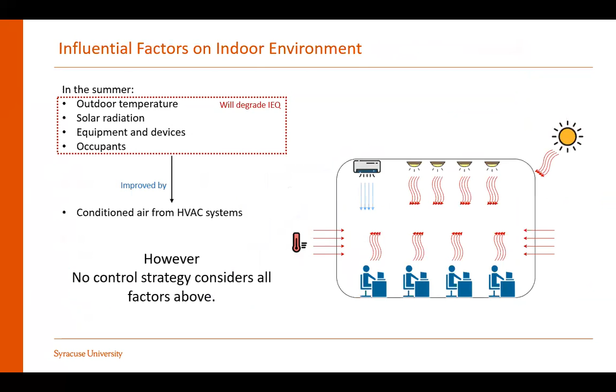For outdoor air quality, we measure those pollutants typically regulated by EPA: PM2.5, NO, NOx, ozone. Those have to be measured. Indoor, we also measure CO2, and the exchange rate is based on indoor air quality. There was a study looking at integrating ventilation and air filtration based on measurement, using this field aspect to see whether we can save energy based on outdoor weather conditions, pollution conditions, as well as indoor occupancy. That's demand based.